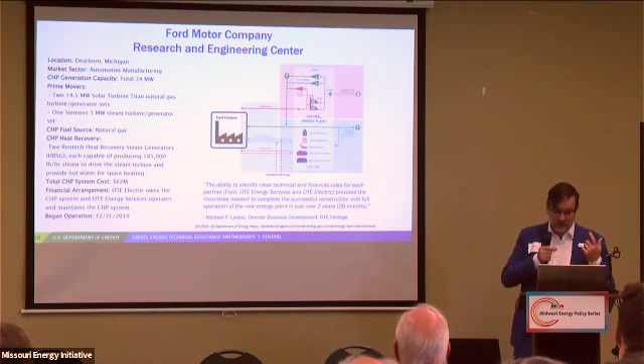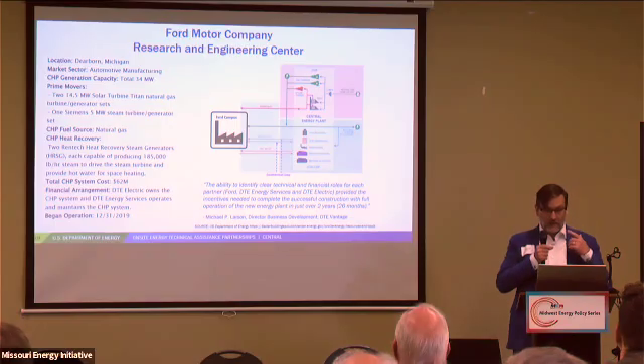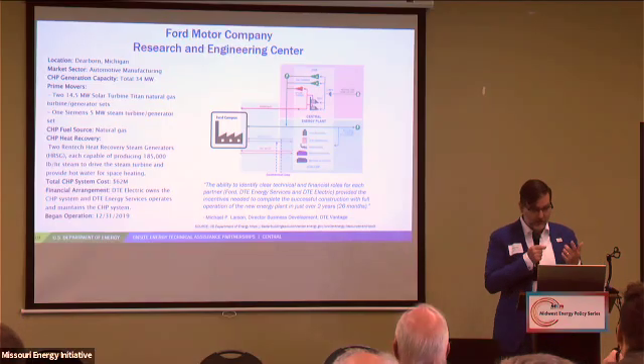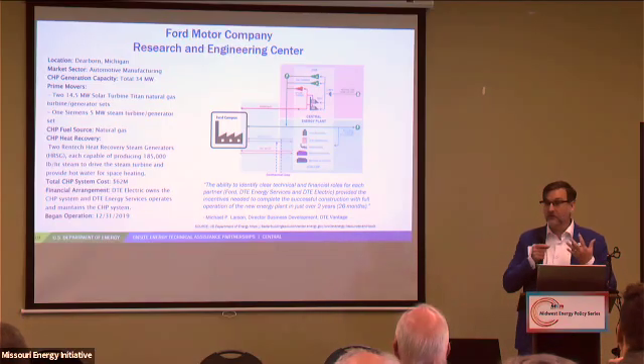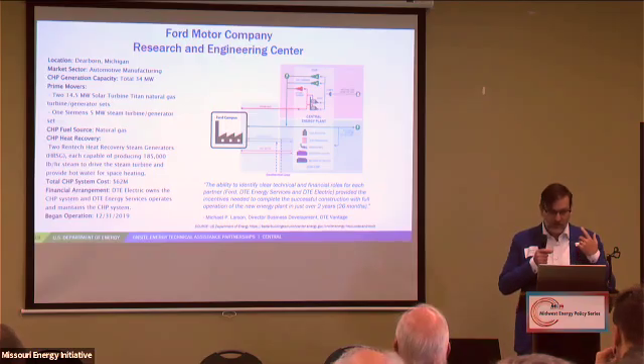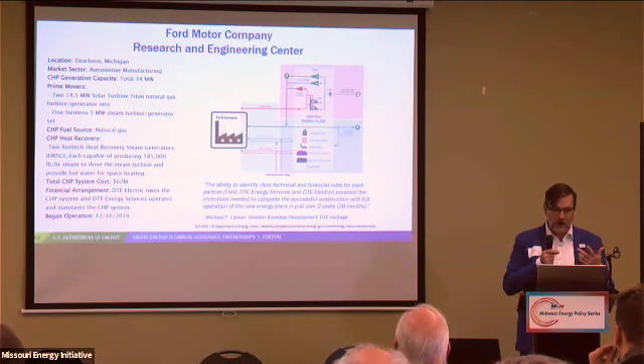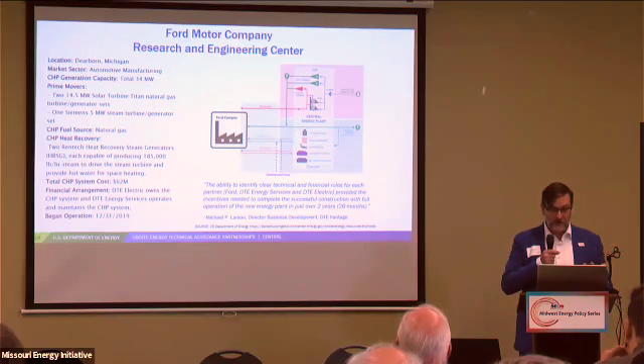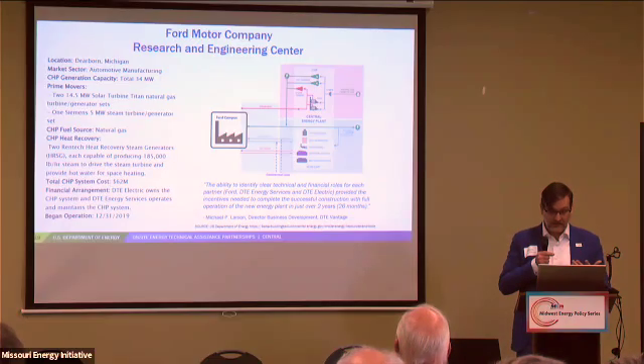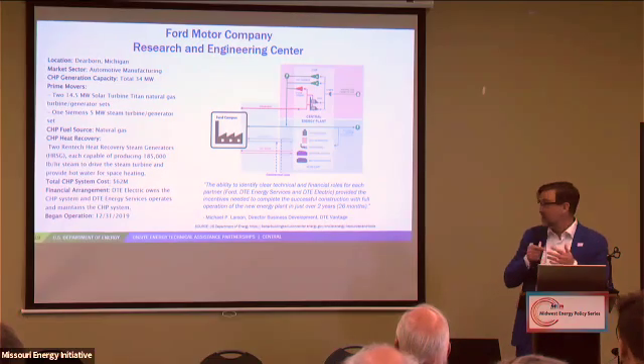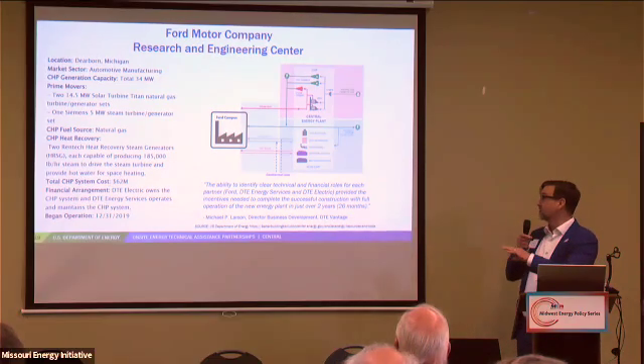They also have geothermal, and they use heat pump chillers. The steam goes to heat pump chillers to produce chilled water. They also have mechanical chillers to provide chilled water, and they use the geothermal to augment the chilled water depending on the price of natural gas. They have heat exchangers to produce hot water from the steam. So you see this kind of complicated box.